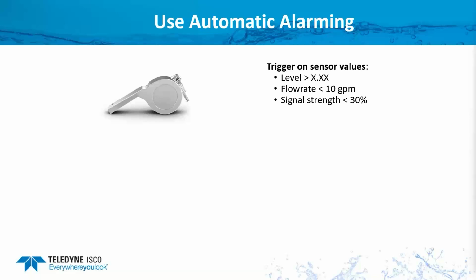because I'm looking at the trends, I don't want to be alarmed when there's just an instantaneous reading that dropped low. Because that could have been due to debris or something coming by and I had a bad reading. I don't want to be alarmed on that. So what I would look for is, I would say, if my signal strength is less than 30% over a period of time, like 30 minutes or an hour, okay, now it's consistently staying low. That's when I want to be alarmed.